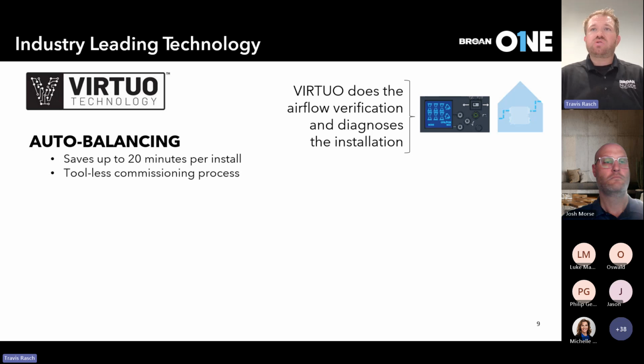If not, on that LCD screen itself, there are two icons for houses, one showing supply air going in, one showing exhaust air going out. One of those two houses will be blinking along with what that maximum CFM that was achieved during that initial startup process. If in that situation we're not hitting the expected airflow that we need for that design, for that application, et cetera, we have now split the diagnostic time in half because we are notifying whoever it is that's interacting with the product, one of these two, supply or exhaust, is the reason you've reached this CFM that's displayed on the screen.